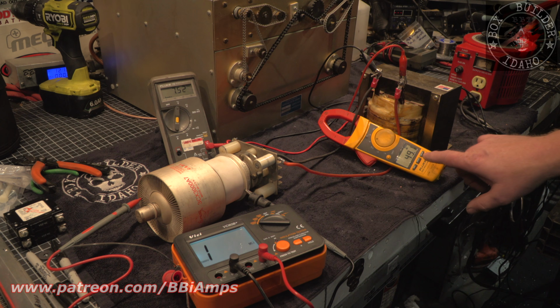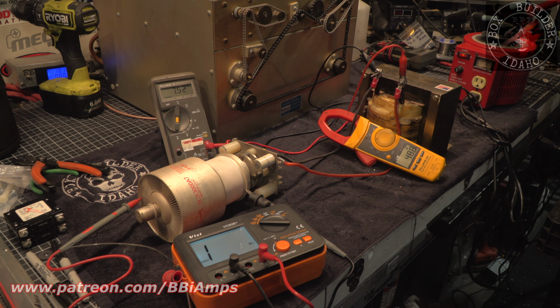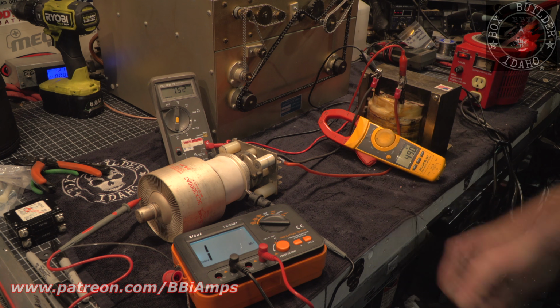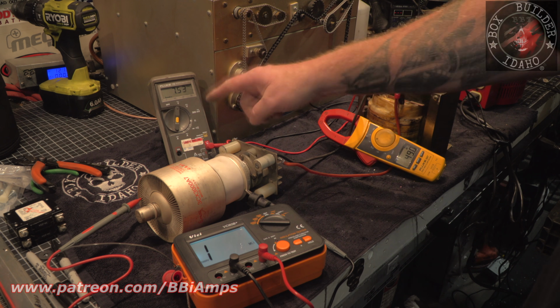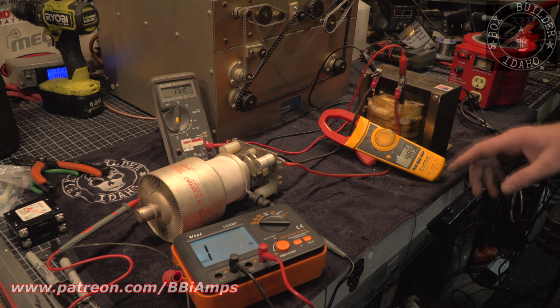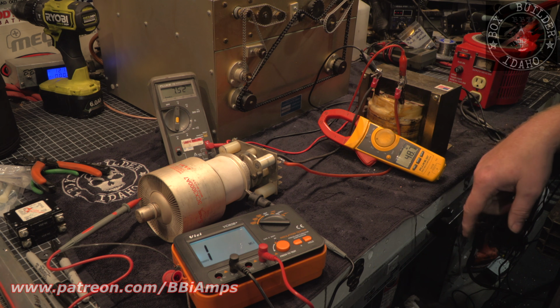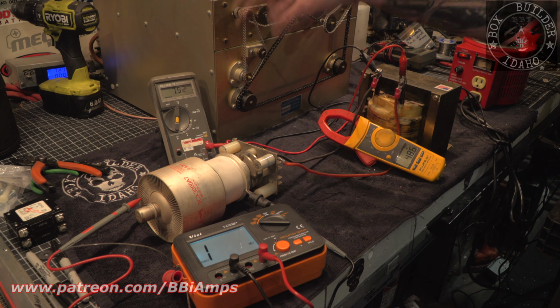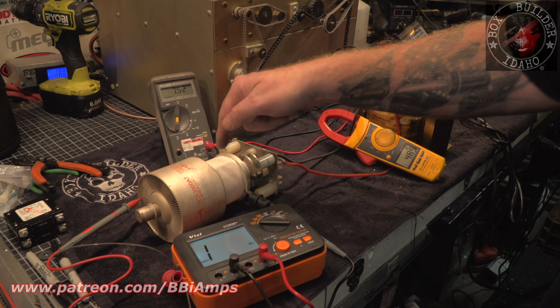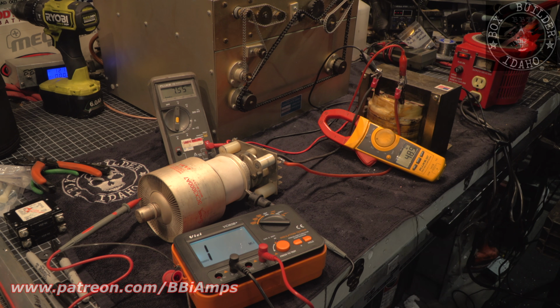7.512 volts, 49.1 amps. It's good. So if this voltage was to unload and take off and go up, and the amp draw to go way down, or for the amp draw to jump way up and the volts drop way off, that would tell me that there's a break in the filament on the inside and that it's shorted.